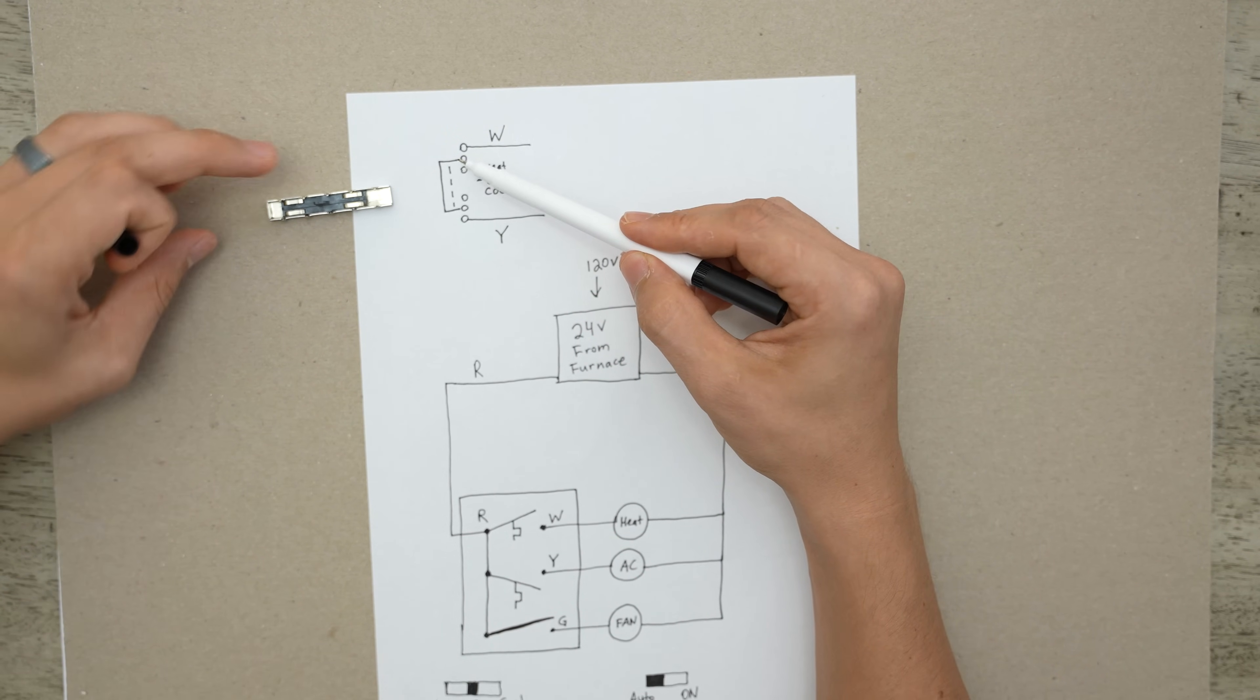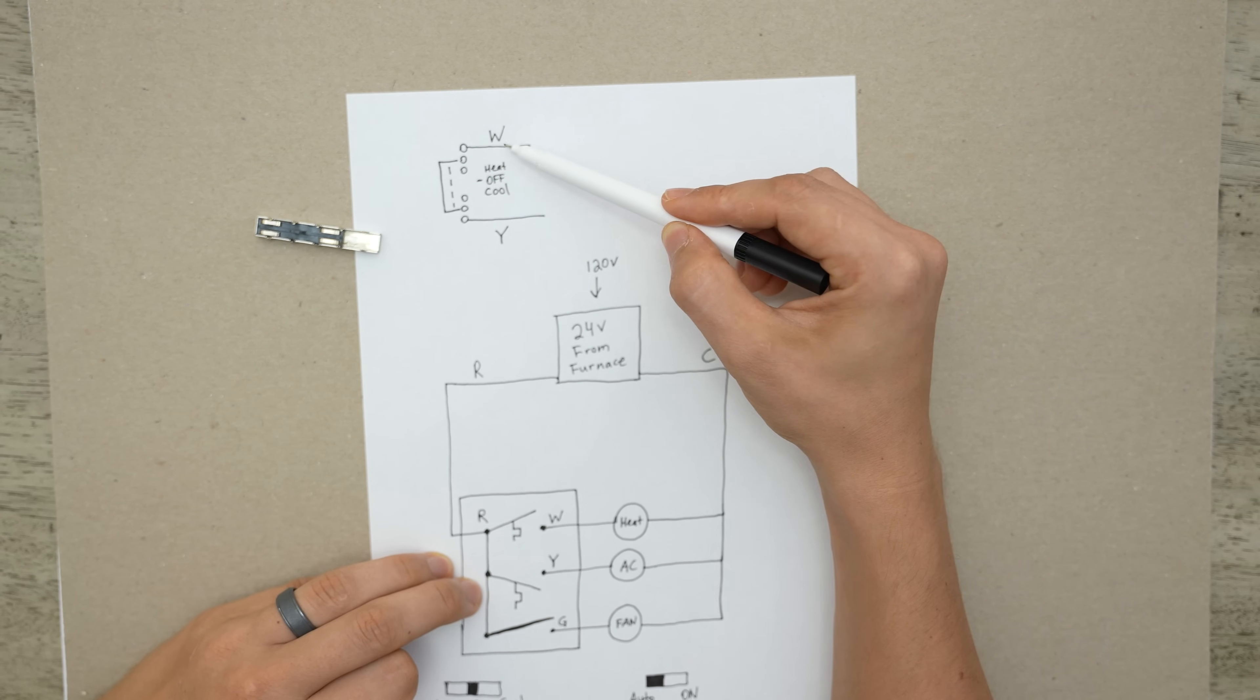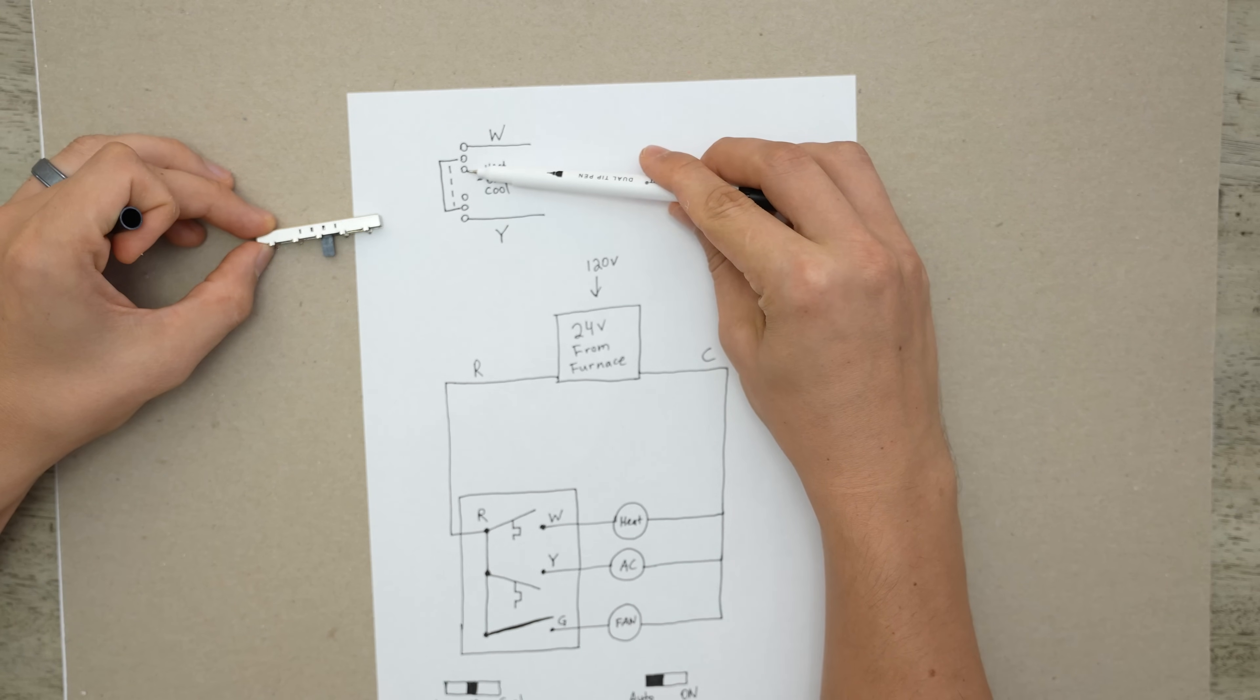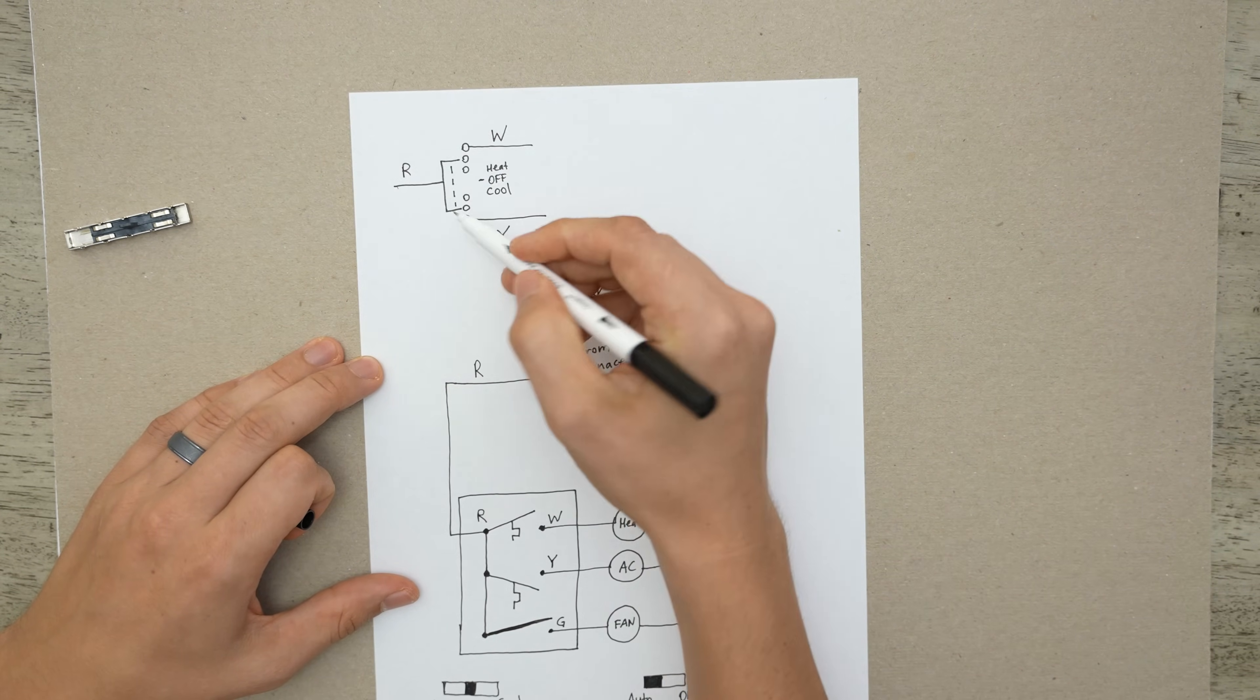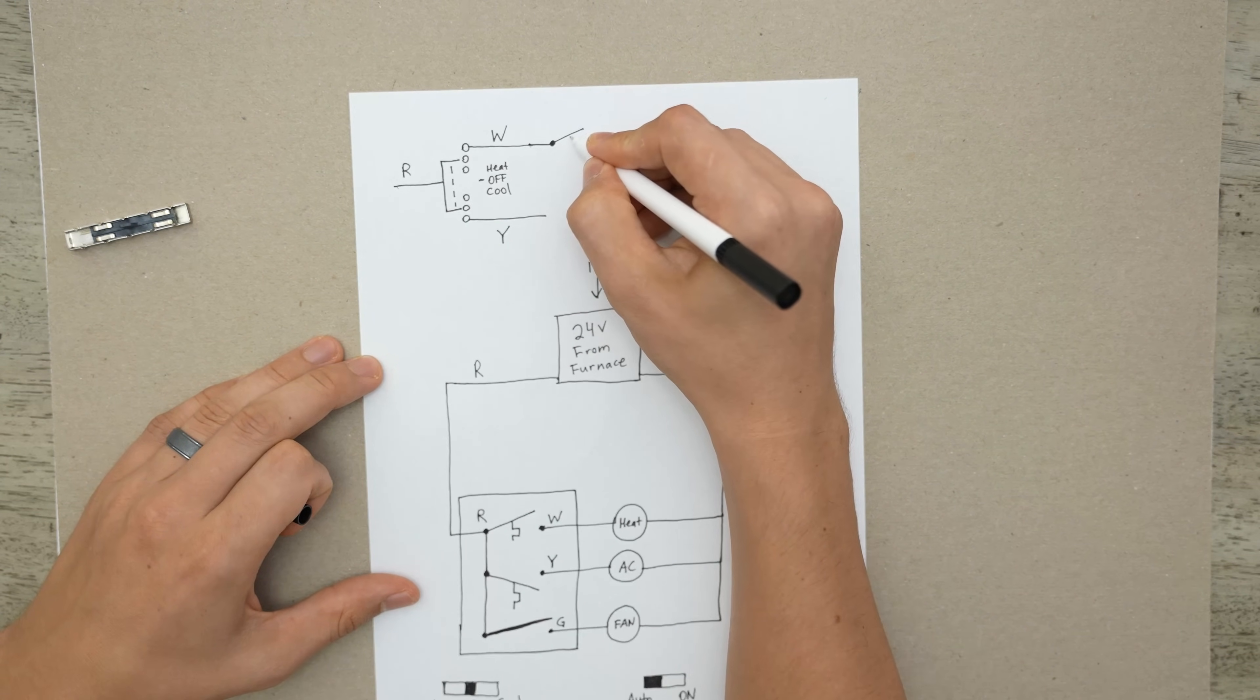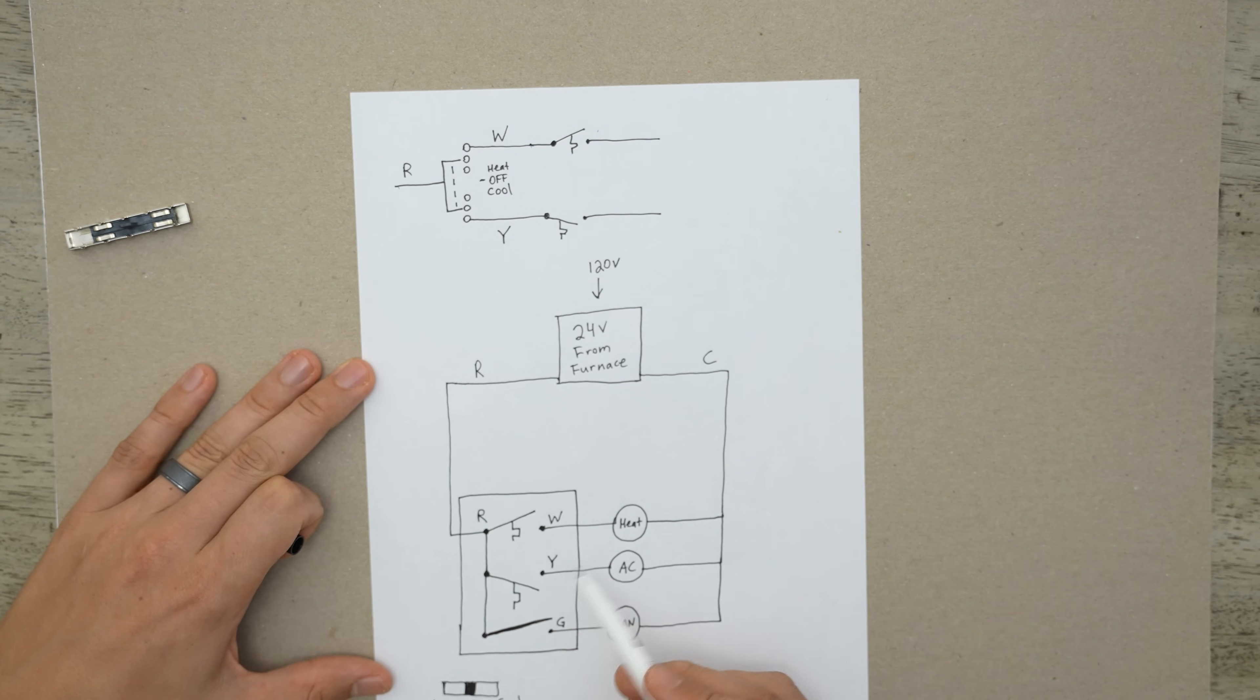So if we move our switch to heating, our switch goes up to this contact and to this contact. Over here, it's a blank. But over here, it energizes our W. And if we move our switch to cooling, if we move it down, this contact gets energized, and this contact gets energized. This one is blank, but this one would power on the AC. Drawing it this way is more complicated, but this would be more accurate. So the power goes in here to the switch. And then from here, it goes to either W, or it goes to Y, which is our cooling. So this would be a more accurate picture than this right here. This is a simplified version.